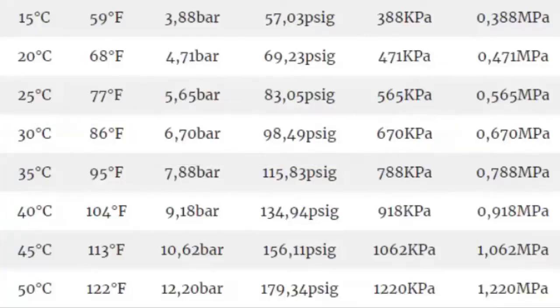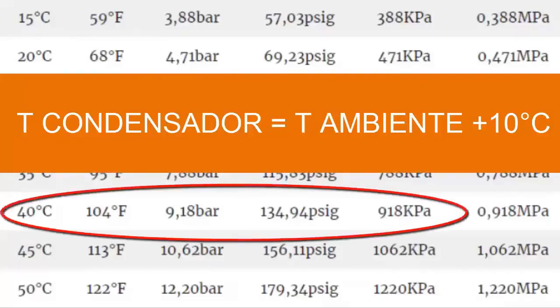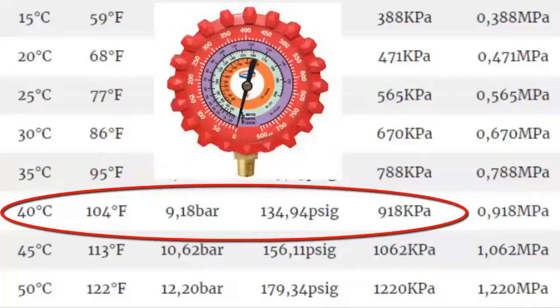2. For an outdoor environment temperature of 30 degrees Celsius, the condenser temperature is usually about 10 degrees Celsius above the environment where the equipment is located. Thus, in the table, for 40 degrees Celsius, about 104 degrees Fahrenheit, the high gauge pressure in the condenser is 9.18 bars, equivalent to 134.94 PSIG or 918 kilopascals.